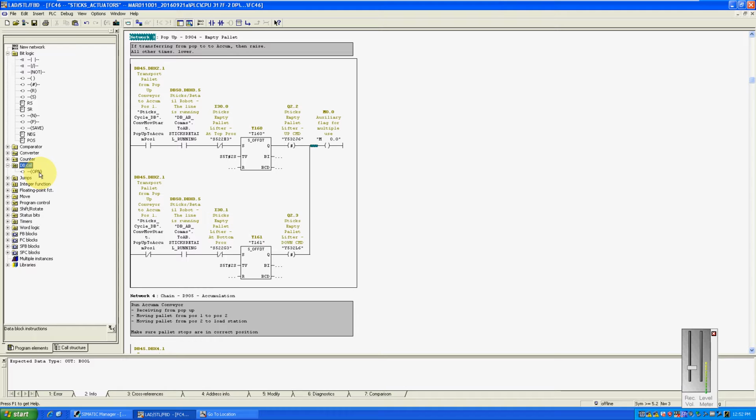DB5.DBB0. If you get lazy, you can open up DB5 and then, because it's open in memory, just access that data as DBB0, DBB2, without the DB5. If you do that, you can't cross-reference the data. They have done it in this code, so expect to find that. So don't use this.